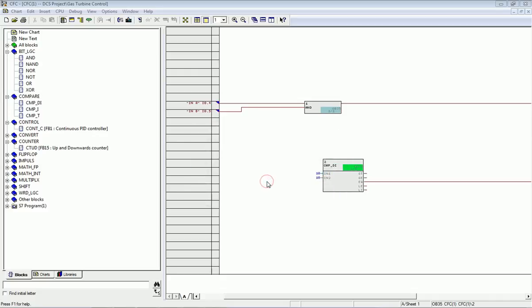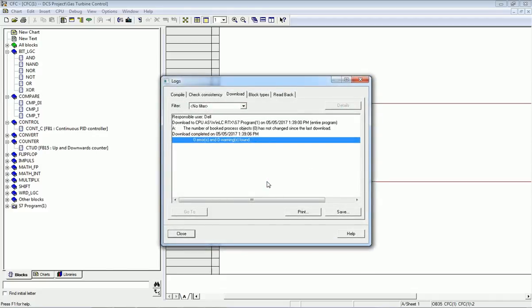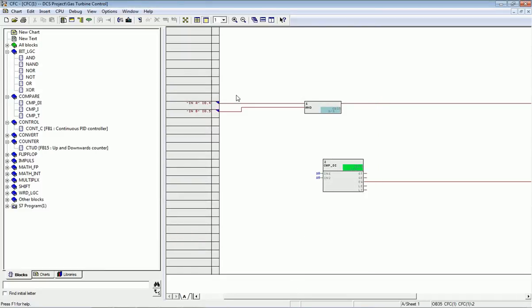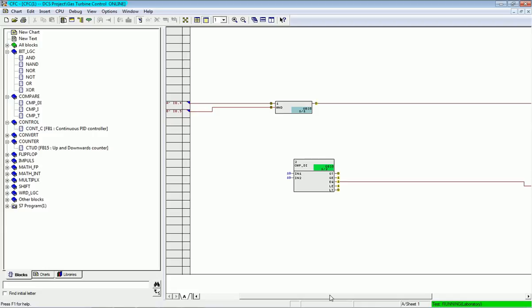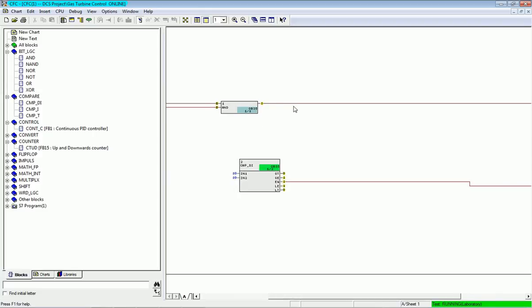The program is already downloaded and we are getting zero errors and zero warnings. I will monitor the window — right now we are in run mode and there is no input at I0.4 and I0.5. I will now give input I0.4 from the automation station, then input I0.5. You can see the values changing in the CFC chart, and on the right side we get an output of 1, as well as outputs for greater than or equal to, equal to, and less than or equal to, since both input values are the same.